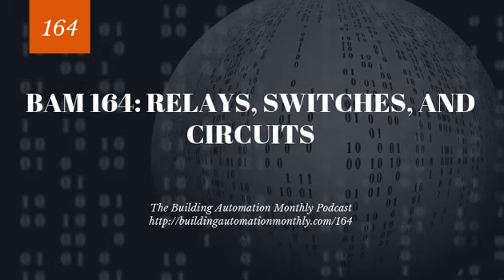Now, with command circuits, we are utilizing relays. And the two main types of relays we utilize are command relays for command circuits and status relays for essentially statuses. So why do we use relays? Well, in order to pull in a large fan starter or heat contactor, that requires amperage. And while some building automation controllers have contacts inside of them that are capable of handling amperage, it's usually a best practice to avoid that. It's a best practice to avoid drawing amps through your controllers.